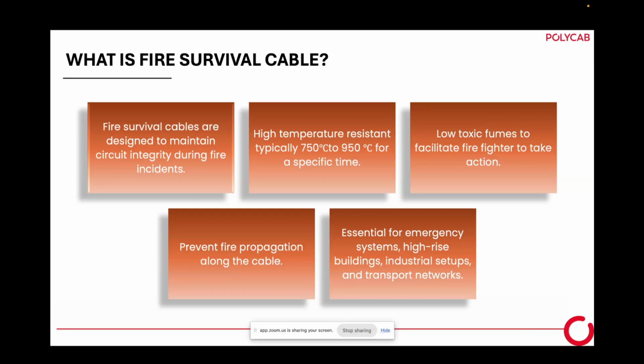Low toxic fumes facilitate firefighters to take action. We've seen many cases where firefighters go to a floor to extinguish fire but fall sick or become senseless. Consider PVC, a highly popular insulating material for wires and cables. When you burn PVC, dark smoke comes out, consisting of carbon monoxide and hydrogen chloride. This hydrogen chloride, when inhaled, goes to the throat and chokes it. People cannot speak, and it slowly goes to the lungs causing pulmonary failure, so breathing problems start.